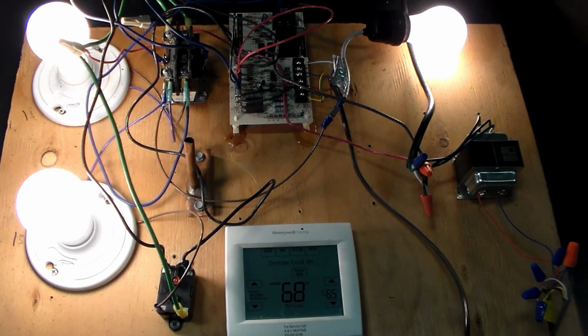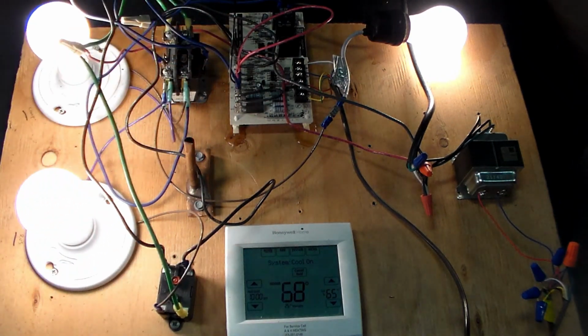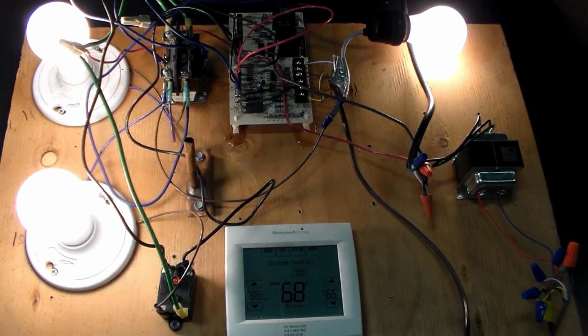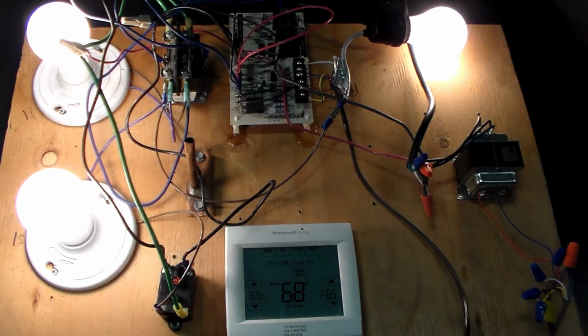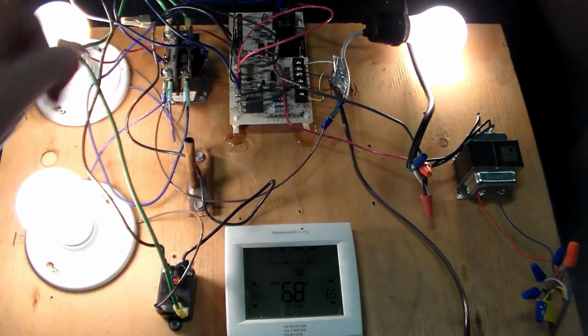So a couple typical things that confuse people on heat pumps is what's that W wire doing? The functionality of it, the fact that that jumper represents 30 minutes of run time, not 30-minute defrost time. What these letters mean, right? Your high pressure, low pressure, your defrost sensor. Once we can get past all of our understanding of that stuff, then the basic functionality of a heat pump, we need to know that the board is controlling the fan. Yes, the power for the fan still comes off the contactor. If the contactor doesn't pull in, there won't be power for the fan.